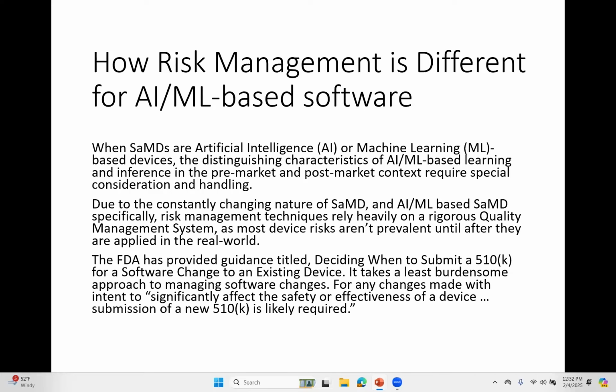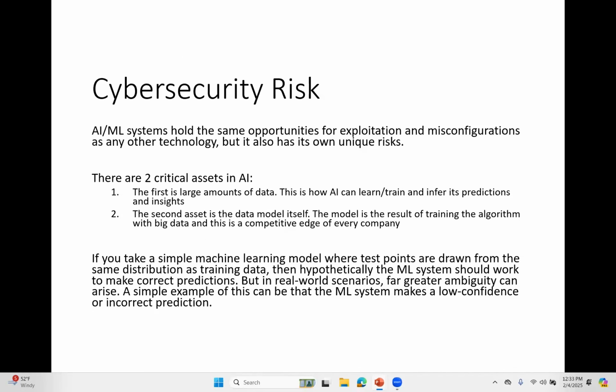So the first place to go to is the 510(k) software change guidance that really talks about the primary issue: do these changes introduce any new considerations for functionality or safety and effectiveness? And if it does not significantly impact safety or effectiveness of the device, then a new 510(k) is oftentimes not required. Again, of course, there are a lot of caveats to that. And as I was alluding to, within AI, cybersecurity is a real emerging space because you have to share and access the data.